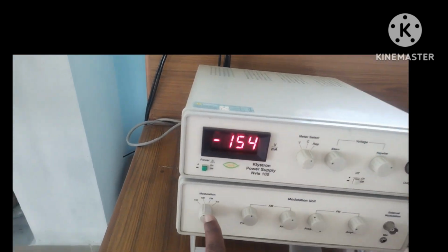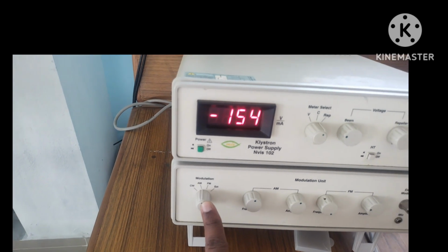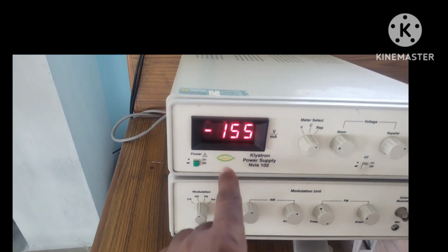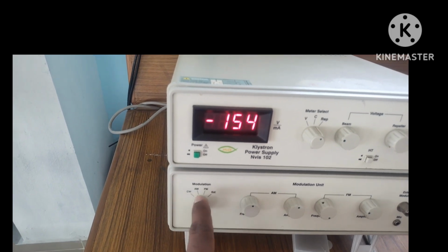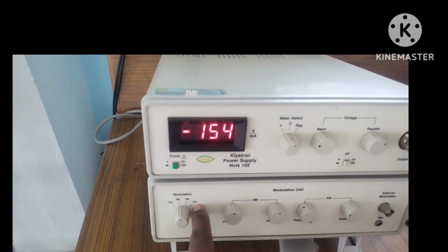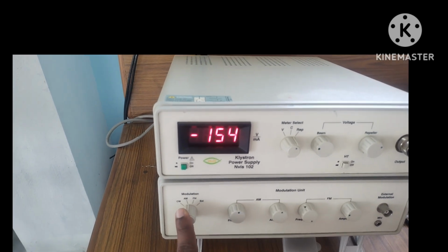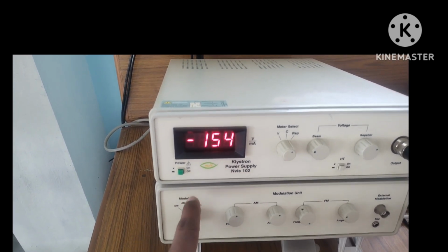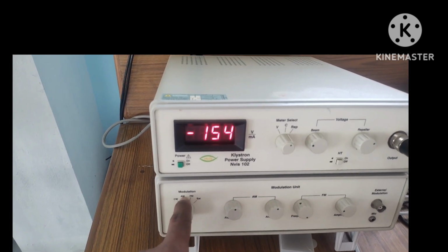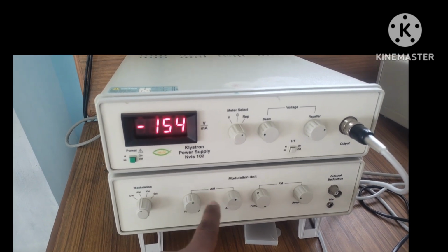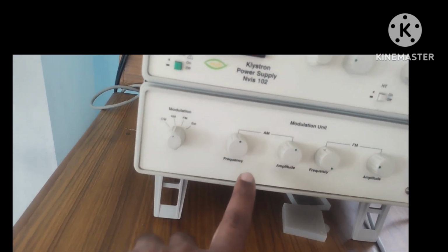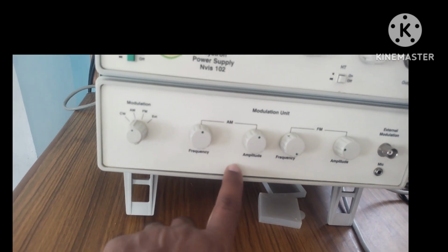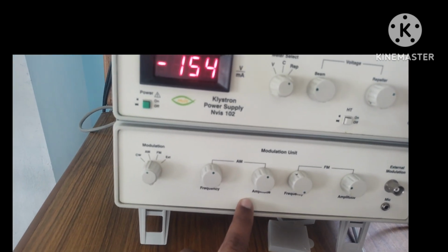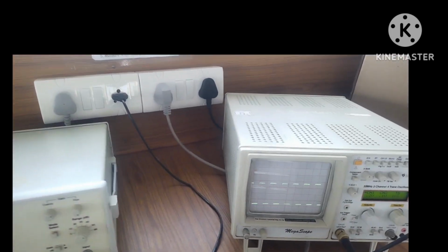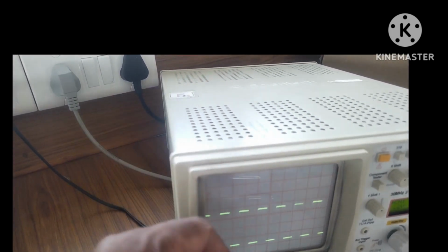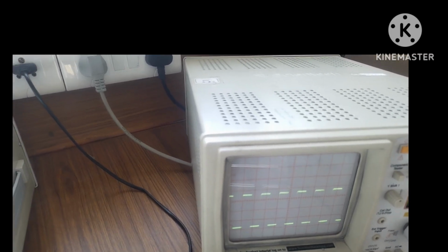Particularly, there are different modes in this reflex klystron power supply. One is the continuous wave, AM wave, FM wave and external mode. Generally, while doing this experiment, the klystron power supply is to be operated in AM mode, amplitude mode. By using this AM, we can get the frequency and the amplitude. When the frequency and amplitude are adjusted, we can get the variation in the CRO, in the amplitude and also the time period.